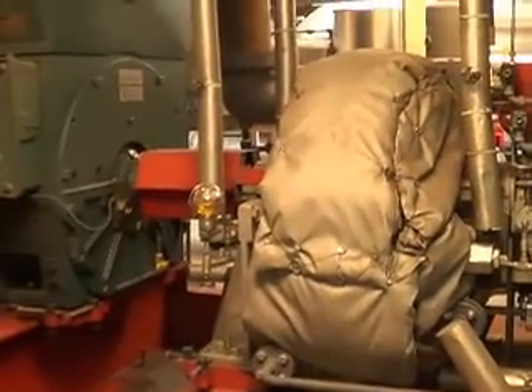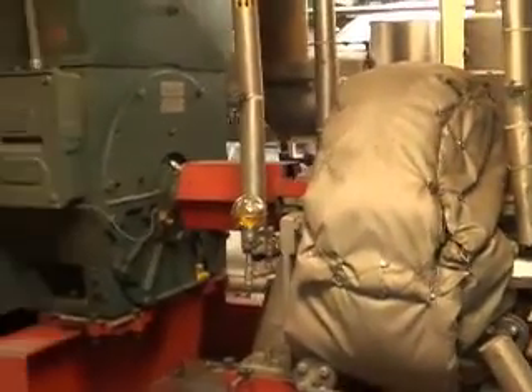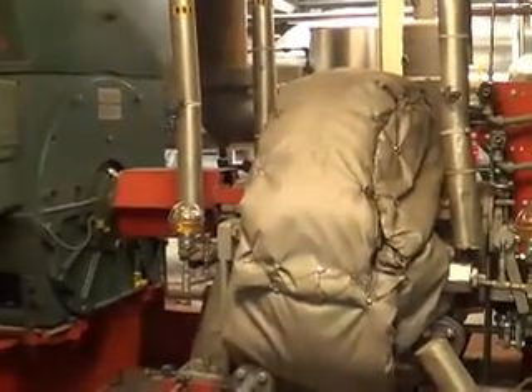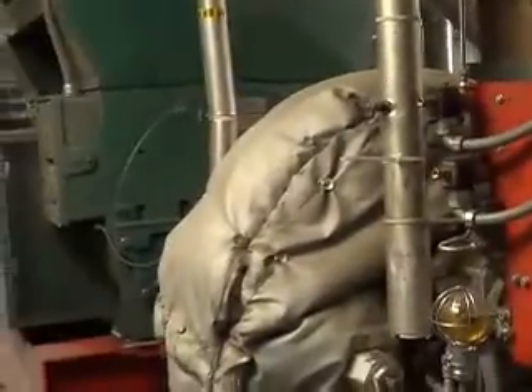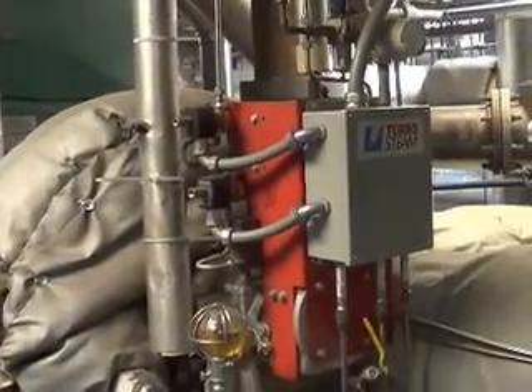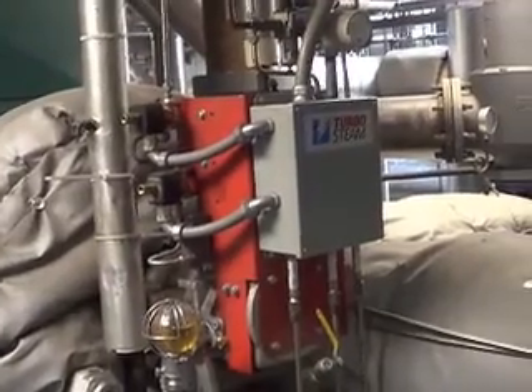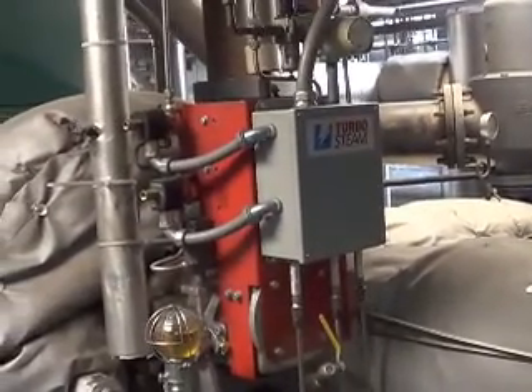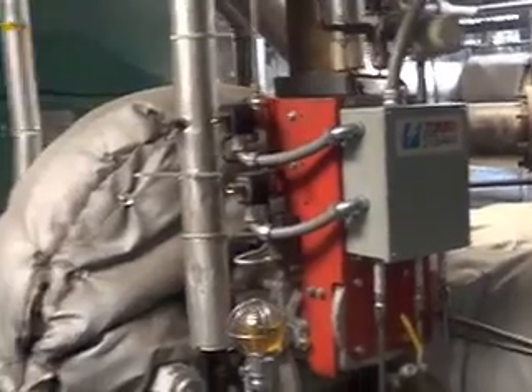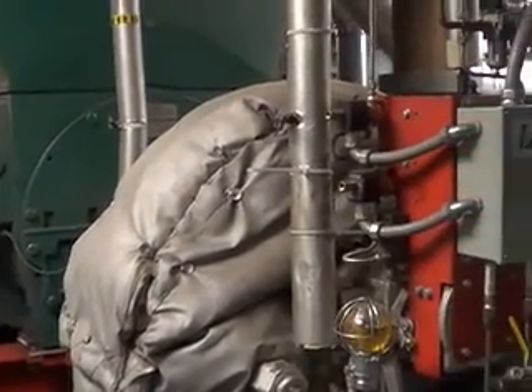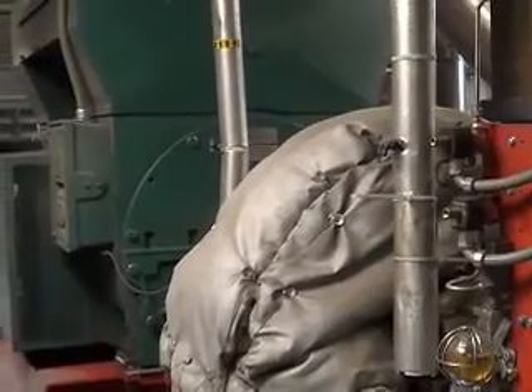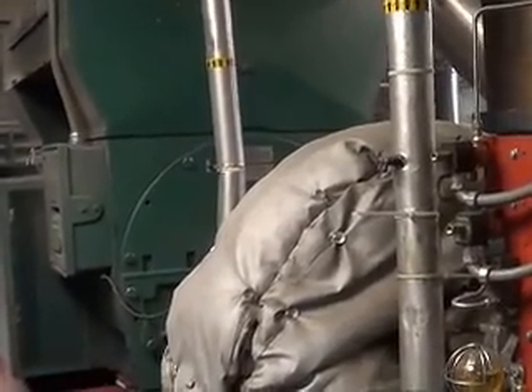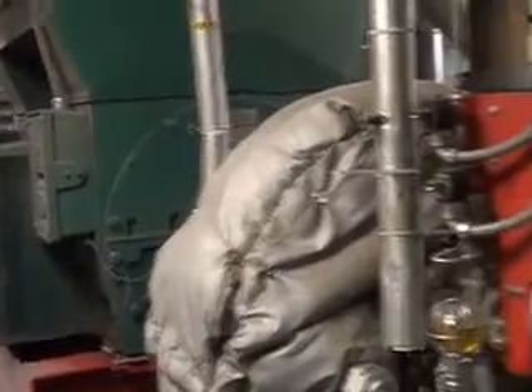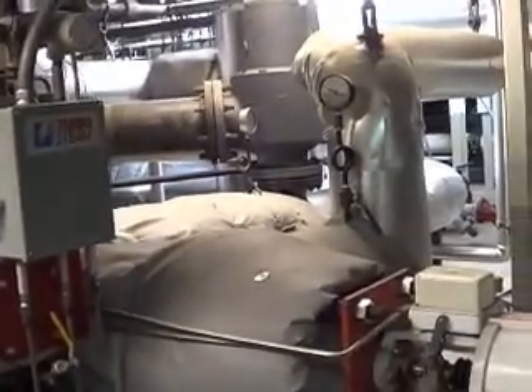The way this works is we make that steam in the boilers, and I've showed you the boilers before. Then we run the steam through this turbine, or these turbines, and it's the exhaust that goes out to the rest of the system to provide heating or whatever the need may be on a 50-pound loop. So it's just more efficient. You're making electricity with your steam, you're taking the exhaust from that electricity and you're sending it out to the load.